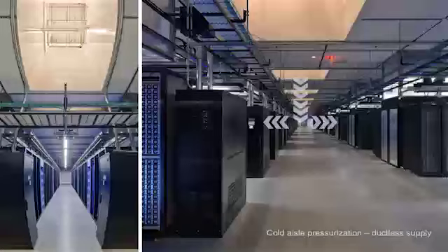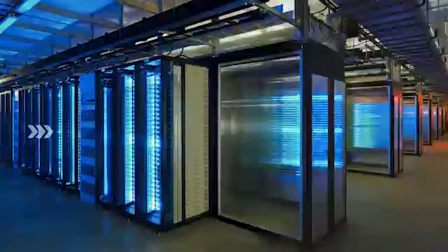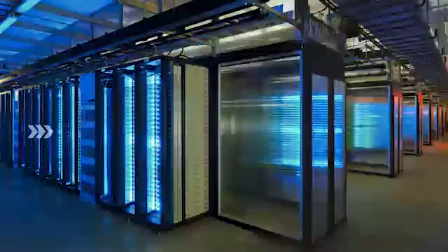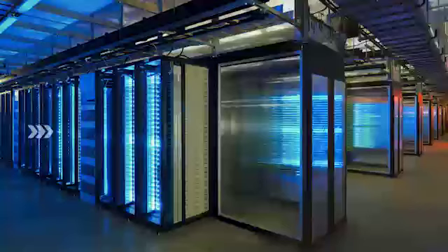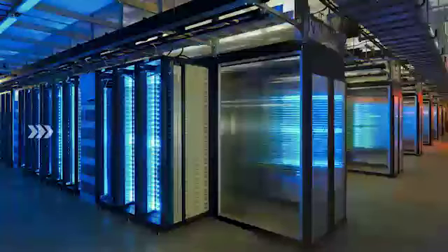We do all our distribution overhead. So all our IT cabling and our power distribution is overhead, no raised floor. Polished concrete floors, just to minimize the amount of material, high durable construction. So the air goes through the triplets and the servers, the DCPS, into our hot aisle containment section. What we've done, based on the lessons from our first deployment of Prineville 1A, was make sure that we had enough row length in our hot aisle containment so that, depending on the changing needs of our server SKUs, we have the ability to accommodate more cabinets.